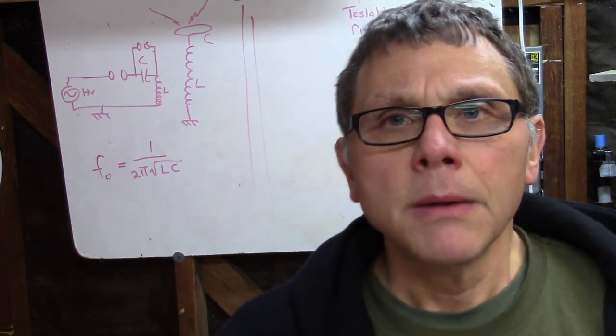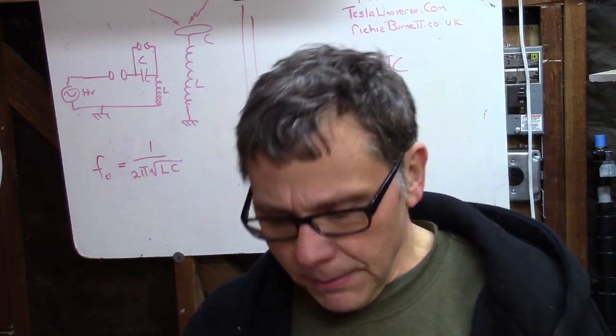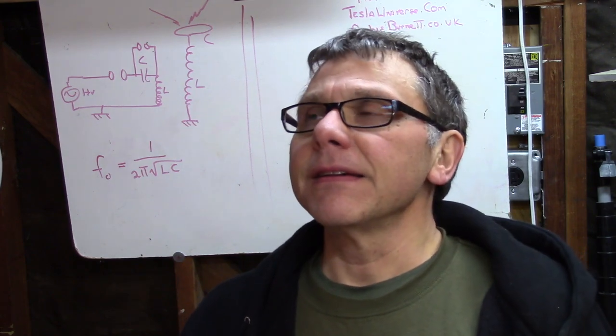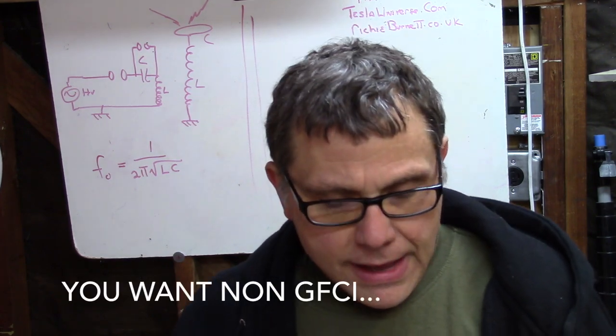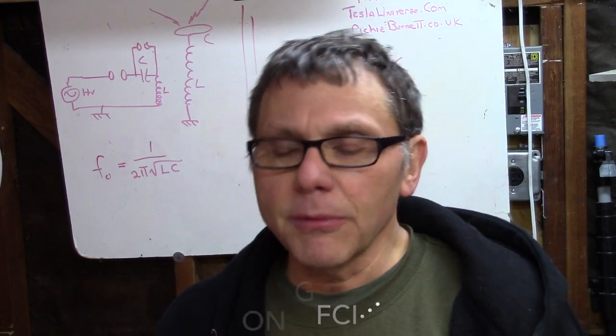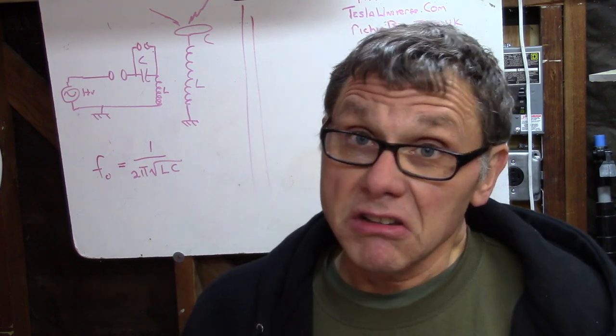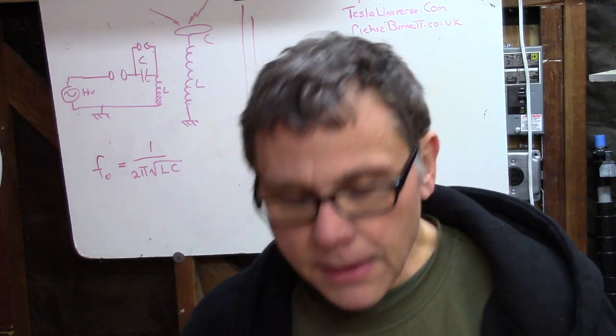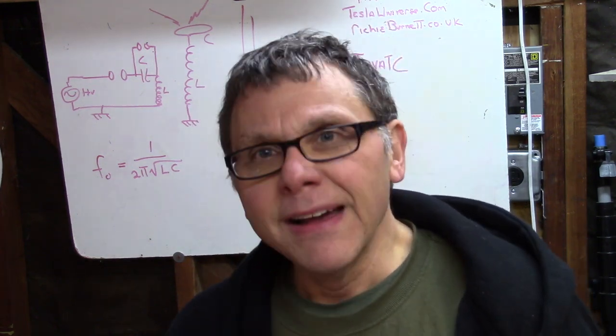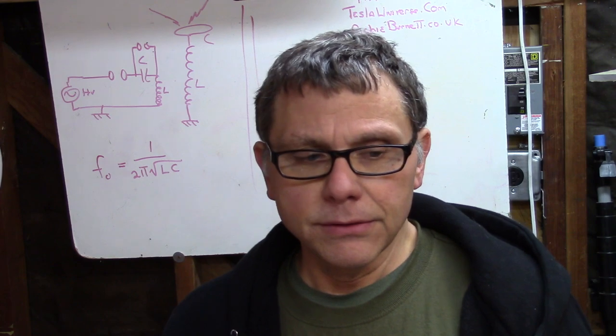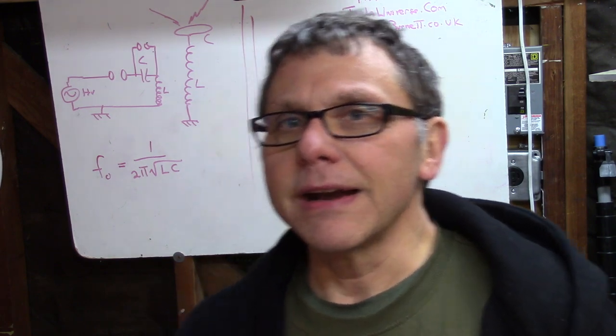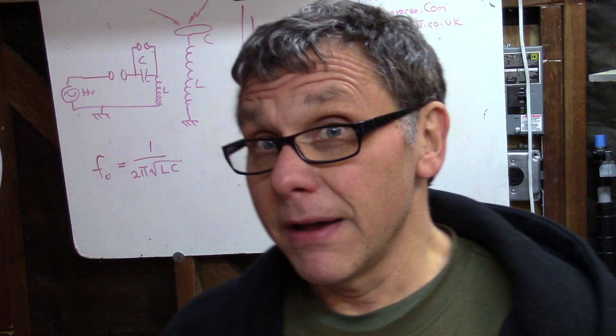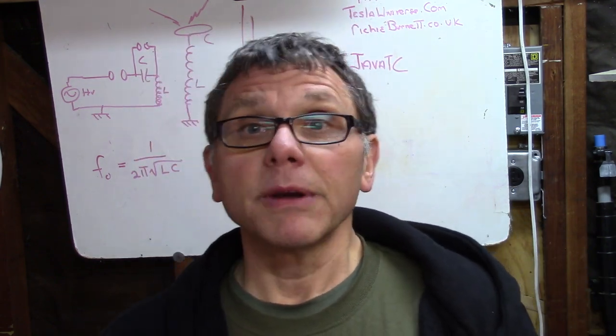The important thing about these transformers is most of the neon sign transformers have a GFCI breaker in them. They're made for signs and made to be safe. So if the terminals get shorted, which could happen because a human is shorting them, the current will be shut off. If you try to make a Tesla coil with a transformer that has a GFCI in it, the GFCI is going to trip. There will be no voltage and it won't work, because you are, after a fashion, shorting the terminals of the transformer.